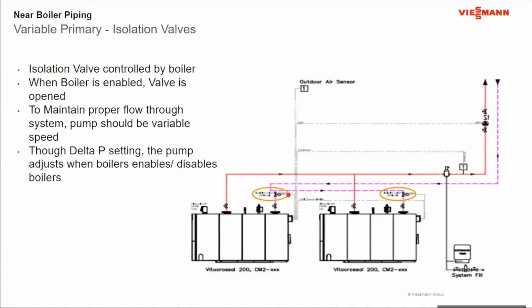Okay, now when I'm doing variable primary, the preference is to add isolation valves to each boiler, and each isolation valve is going to be controlled by the boiler. So when the cascade enables a boiler, the boiler opens up its isolation valve. This way, I'm only moving water through the boiler that's on service. And in variable primary, because this pump is going to have either a VFD on it or it's going to be ECM, and there's a good chance that it's going to work off of delta P, differential pressure, when the valves go open and close, the pump will adjust for the change in the dynamics caused by pulling that boiler out of the circuit, and it will adjust the flow accordingly. Again, by doing this, the system delta T and the boiler delta T are the same, and I'm only moving water through the boiler that's required, and the pump will adjust to a lower flow rate to accommodate this.